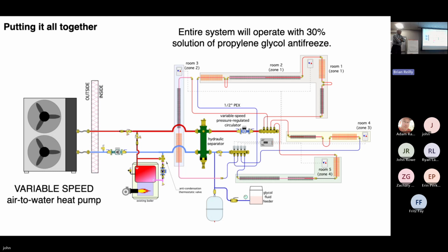In general, the air to water heat pump is probably going to do better than the heat pump water heater as far as COP goes, especially in the summer when it's really warm outside. That system I mentioned in the parsonage, in addition to the panel rads, uses a TurboMax tank. I don't know if you're familiar with them. They have internal coils that domestic water goes in, and the shell of the tank is the mass of the water. We use that tank as both a buffer for space heating and a preheat for domestic. We're going to heat that tank at most to about 110 degrees for those panel radiators. That's not quite warm enough for the domestic, but it's a very good start. Fantastic start. It's better than 50.